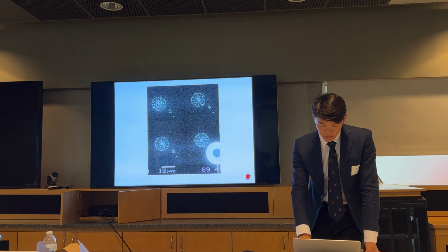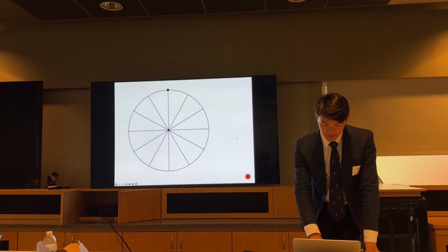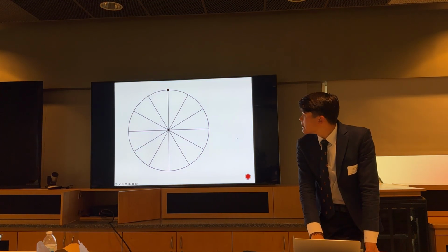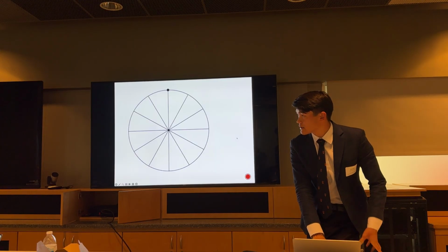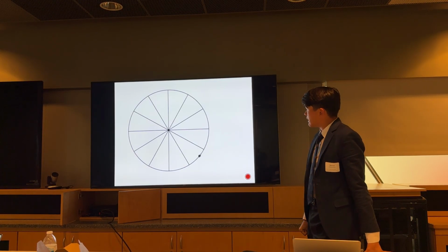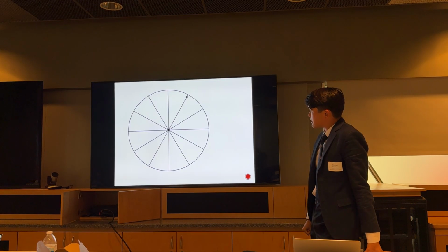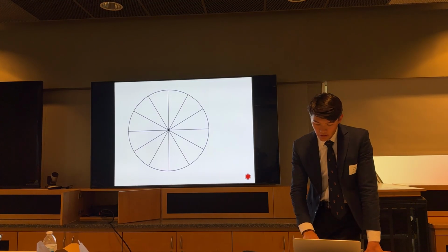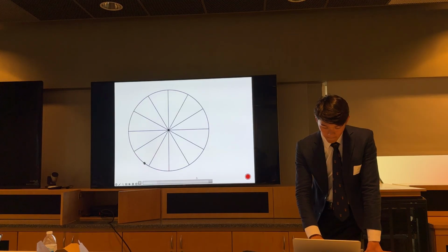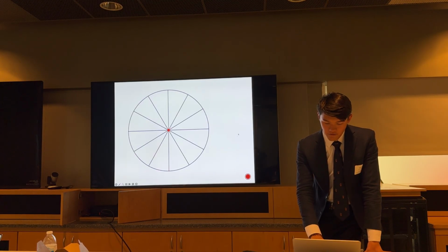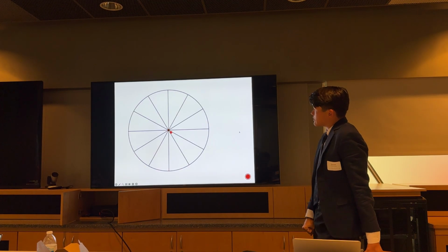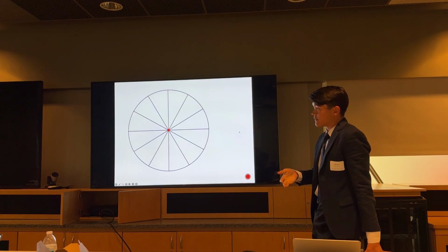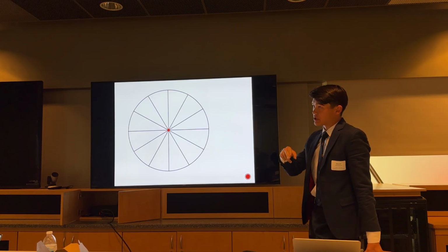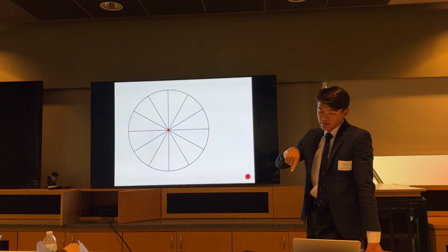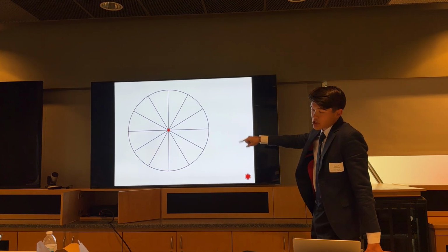And I can show a rough animation of what it was like. So here's what's supposed to happen. The black dot shows the desired position of the electron beam, and it goes around and exposes the surface of the PMMA and draws the pattern that we want. However, there was likely noise introduced into the position signal of the electron beam because the position was actually encoded by just an analog voltage. So there was likely noise causing a digital jump like that.